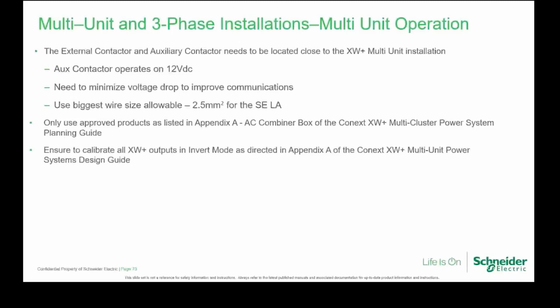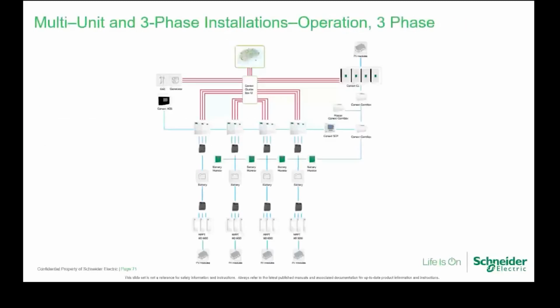And you can also calibrate the output of all the XW Plus units in invert mode as directed in Appendix A of the Conext XW Plus multi-unit power system design guide. Those are the two documents I was referring to earlier, the ones that are available from our website. So this is not a typical system, this is actually quite a large system, where we have a cluster of four inverters per phase. That then goes back to the cluster box. Then you hook up your Conext three-phase inverters, your generator and your grid. That will then provide a microgrid system, say for a remote community. And this is actually a hybrid solution where you have solar charge controllers as well as PV string inverters.